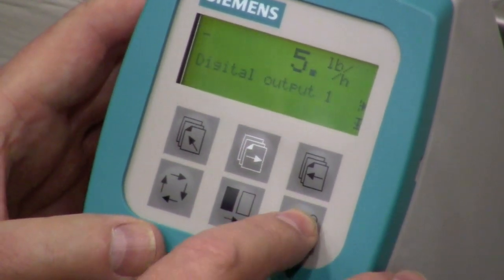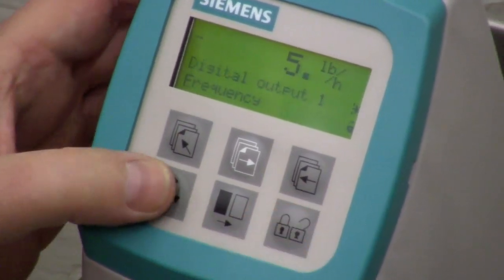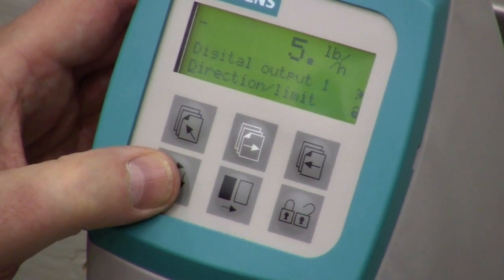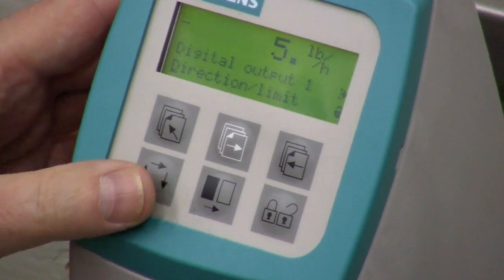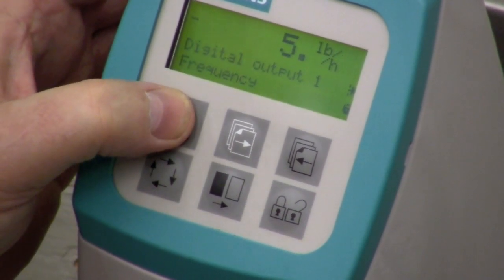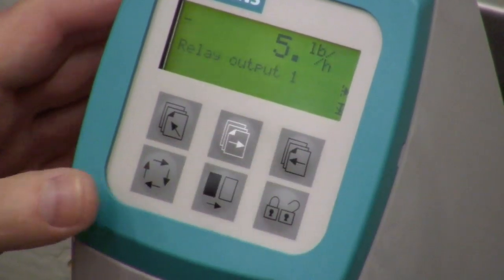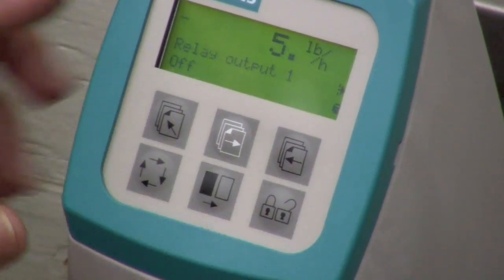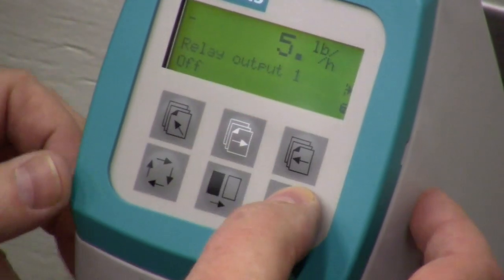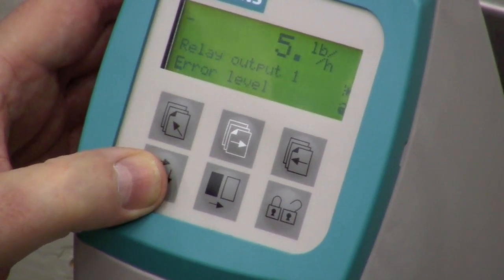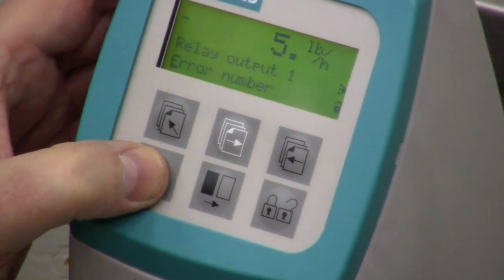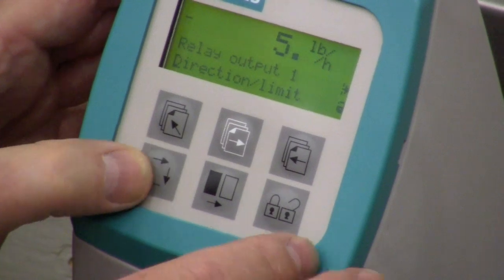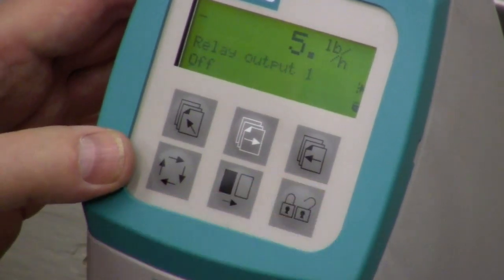Then you have your digital output — how you want to set that up. Frequency is generally what you'll have it set to. Error level, error number — basically you can get a direction limit, and you can set it up to get a digital pulse when one of these errors comes up, monitoring it downstream as more of an error-checking application. For relay outputs, you can set this up to turn things on and off based on a set point. It's currently set to off. You could unlock it and change it to error level, error number, direction limit — in our case we'll just keep it off.